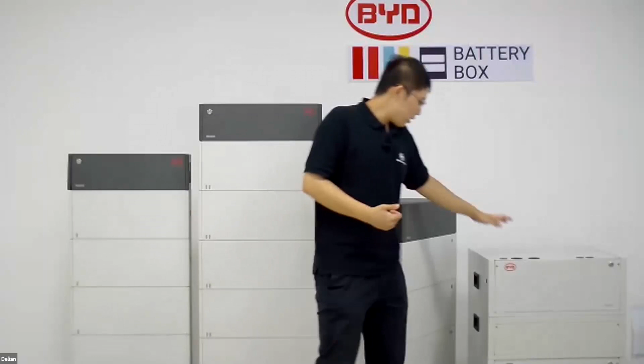We use the LVL a lot for off-grid projects or small commercial projects because of the large scalability. As you can see here, we have two systems of the LVL. You can stack one system on top of another, which saves a lot of space. One system is 15.4 kilowatt hours, so two systems give you basically 30 kilowatt hours in a very small size — 1 meter tall with 30 kilowatt hours of usable energy.